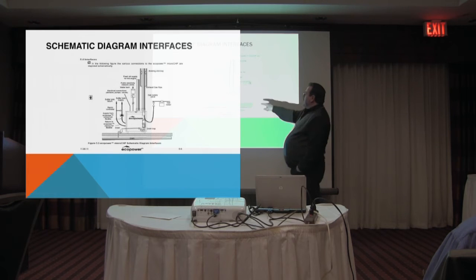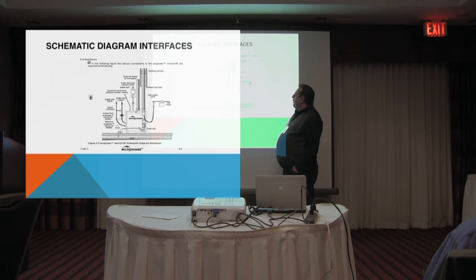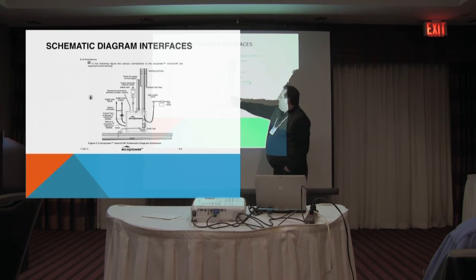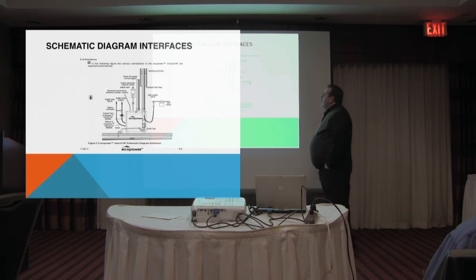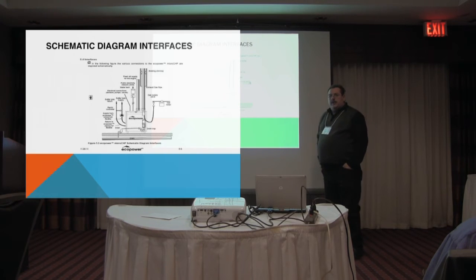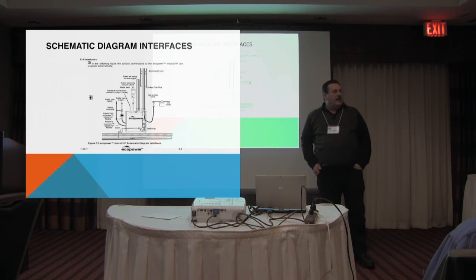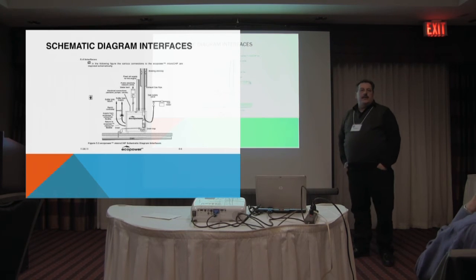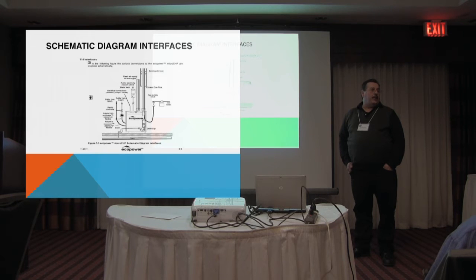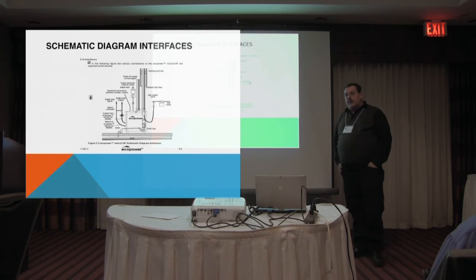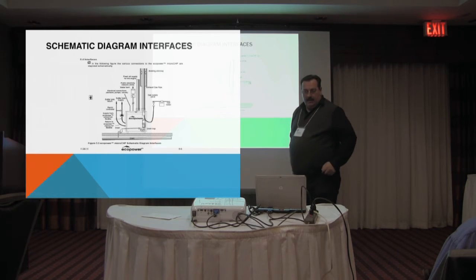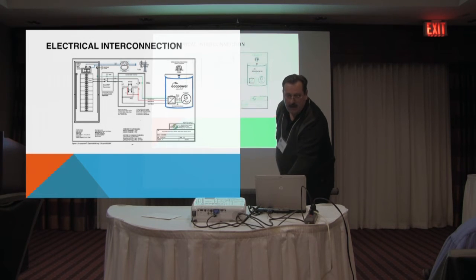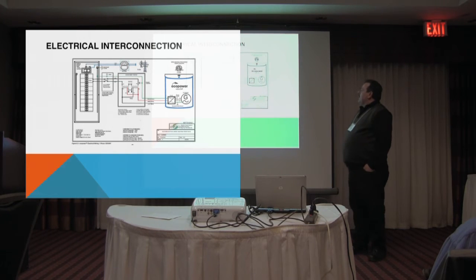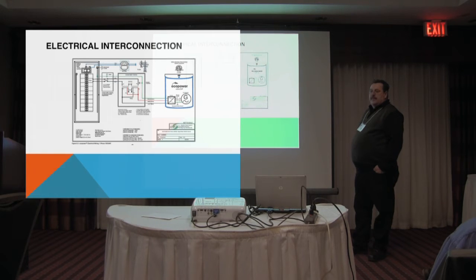So as far as integrating in the system, you've got your venting, you've got your gas supply coming in, and then you've got your water side going out to your storage tank, and then the only other interface will be the electrical interface between the unit and the panel. This being a 4.7 kilowatt unit, that interface is simply a 10-2 wire running to a 30 amp breaker in the panel through an isolation transformer. So this gives you a bit of an idea of that electrical interconnection. The isolation transformer is there as a safety, and we're putting power back onto a 30 amp circuit. It's going to feed back into the house.